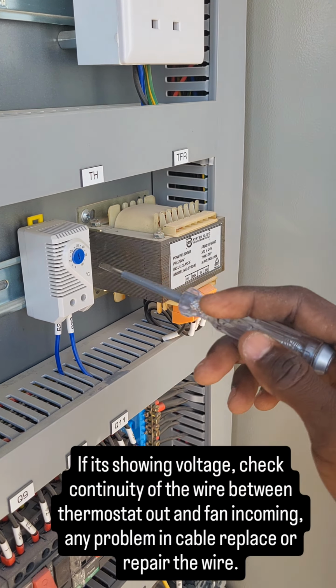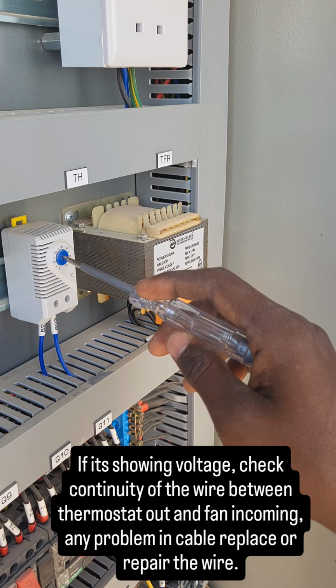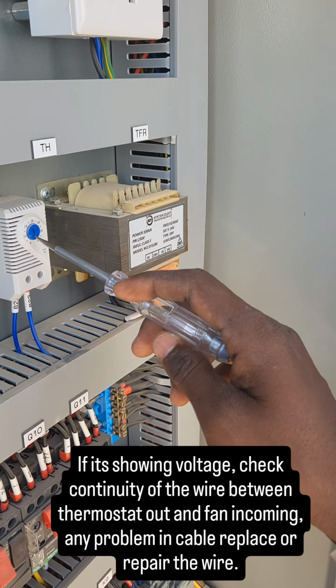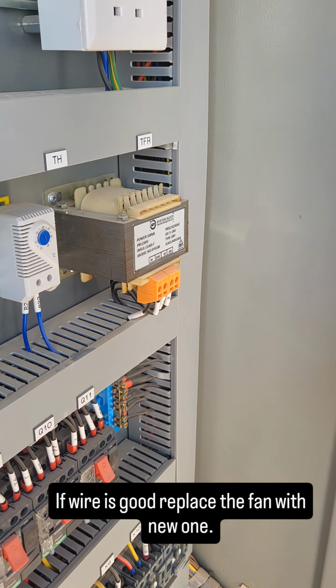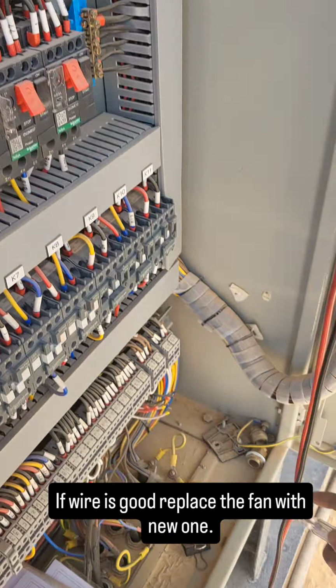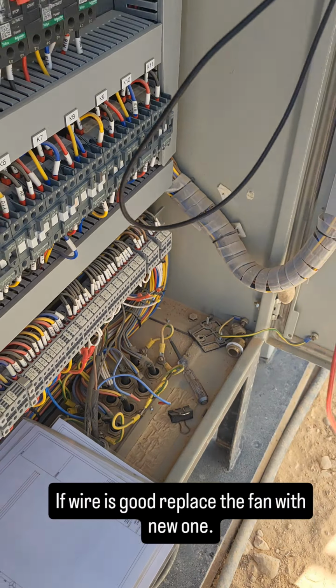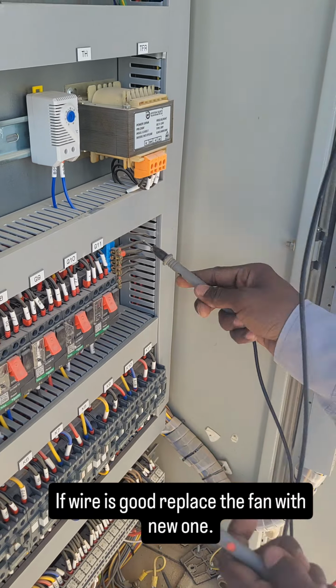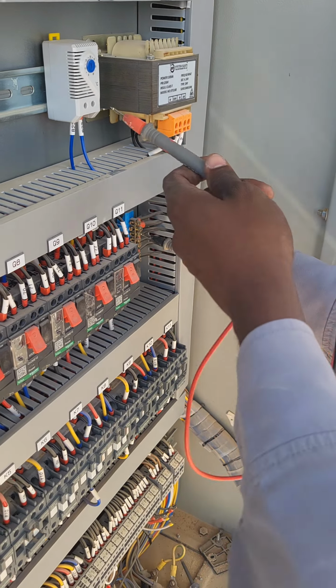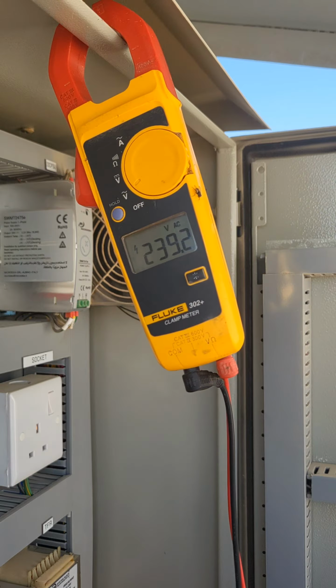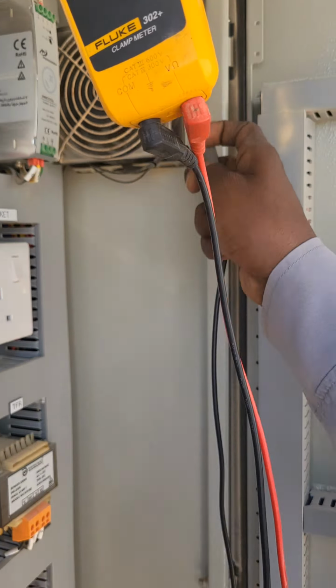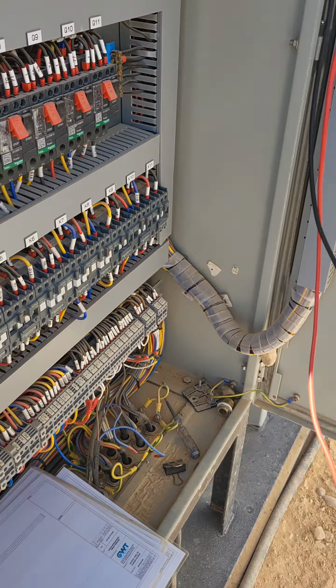The only problem is that the thermostat didn't satisfy the set temperature, so there is no issue in the electrical circuit. Now we will check the voltage from the thermostat out to the neutral. One probe on the neutral and one probe on the thermostat out. Check the voltage: 240. So the circuit is good. This is how we troubleshoot with the drawing.